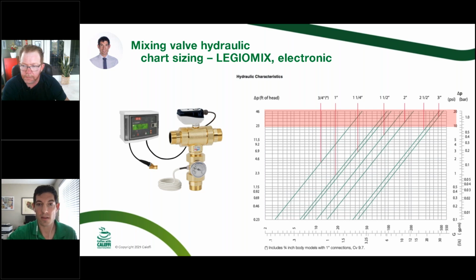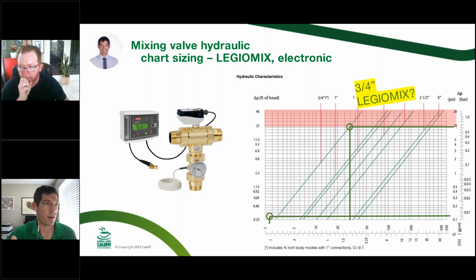All right, so I've got the similar chart. We've got the red shaded area at the top with that 10 psi drop. The crazy thing with this one is, with the flow conditions that we have, that 2 to 30, you could go all the way down to a 3/4 inch Legio mix. Part of the reason is that they're inside of the chamber. The CV of these valves is a lot better because it's like a wide open ball that's modulating, instead of a tight passage through a cartridge that slides up and down.